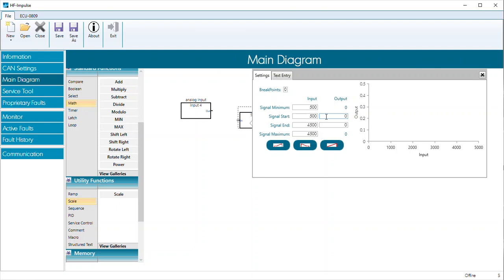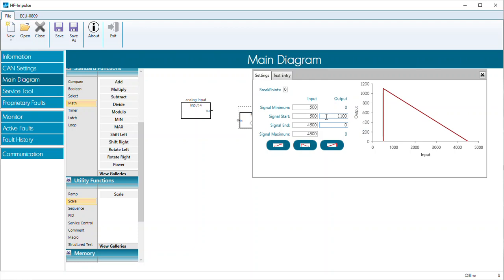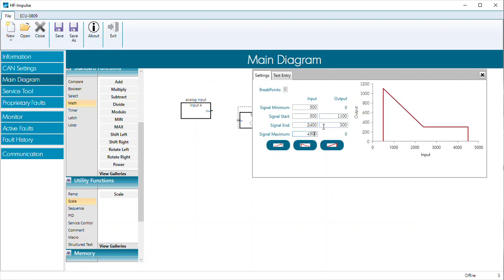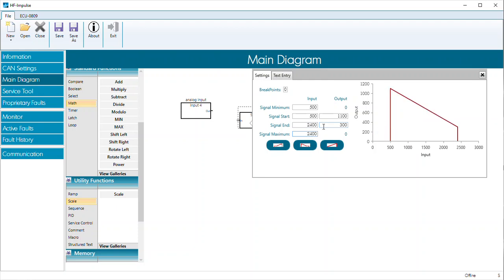The values I'm using aren't necessarily the final coil values — you'd have to figure out what coil you're actually using, be it a 12 volt or 24 volt, and put in the correct numbers. But for our example, running from 500, the signal maximum is 2,400. So from 500 to 2,400, I'm going to run a current from 1,100 to 300. We can see that graphically represented here.